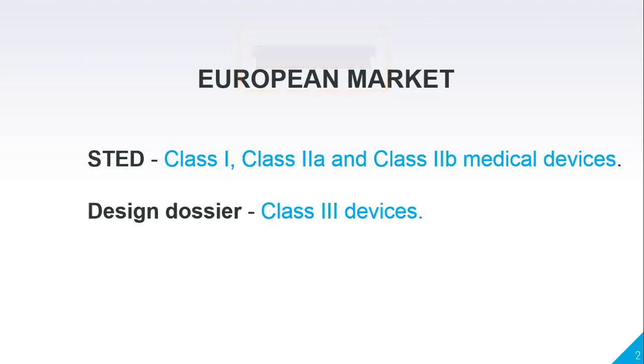Then that government reviews your application, and approves it if it satisfies the requirements, right? So you can tell me now, who can prepare the STED? Manufacturers. Right, very good. The manufacturer has the responsibility to prepare the STED. Good. So this technical documentation was developed to drive more standardization of medical device regulatory submissions across markets.